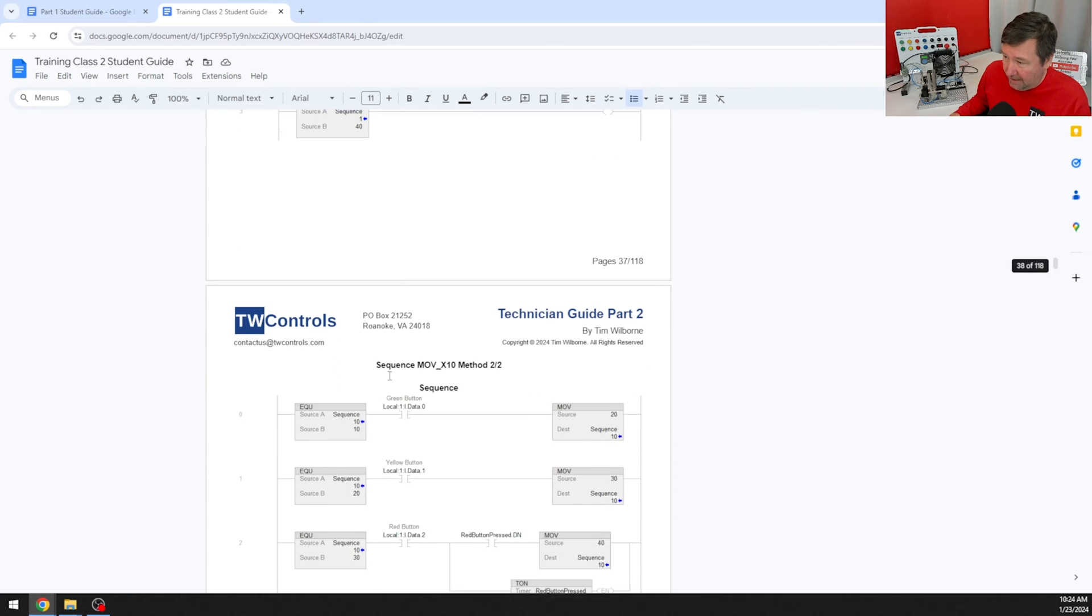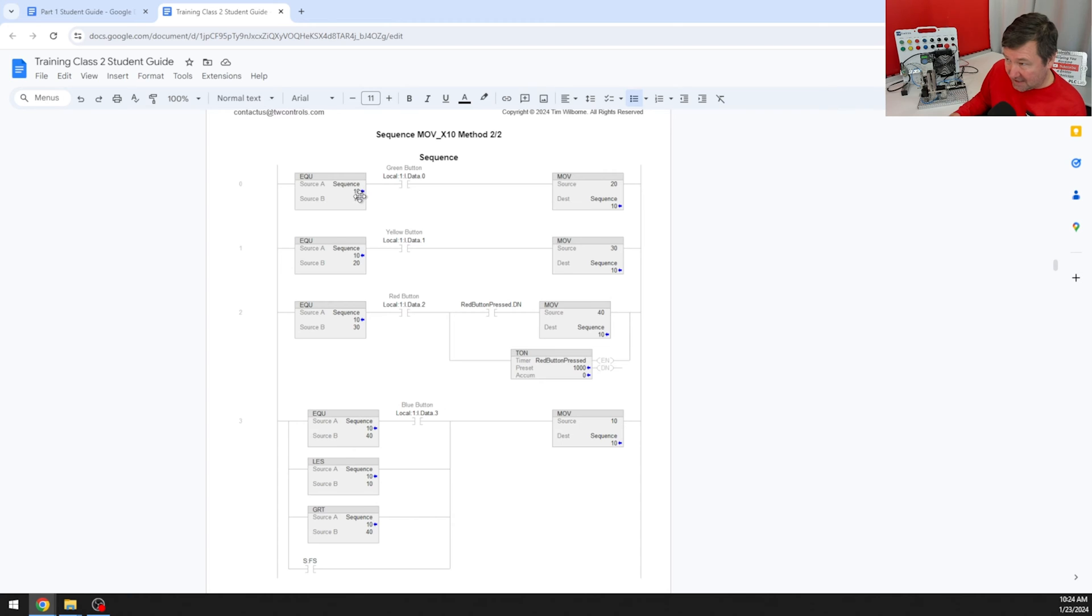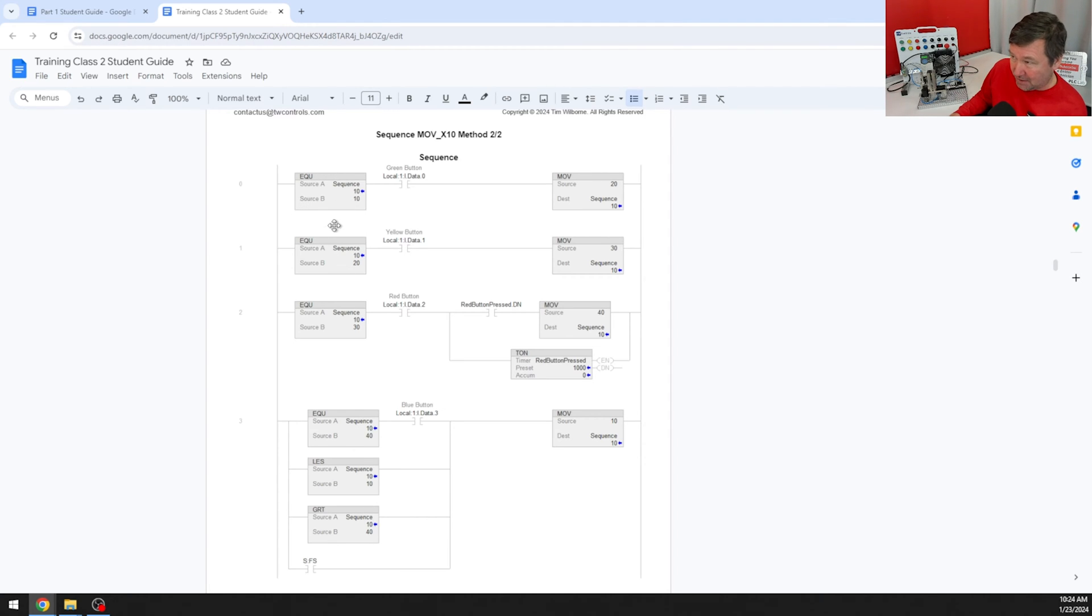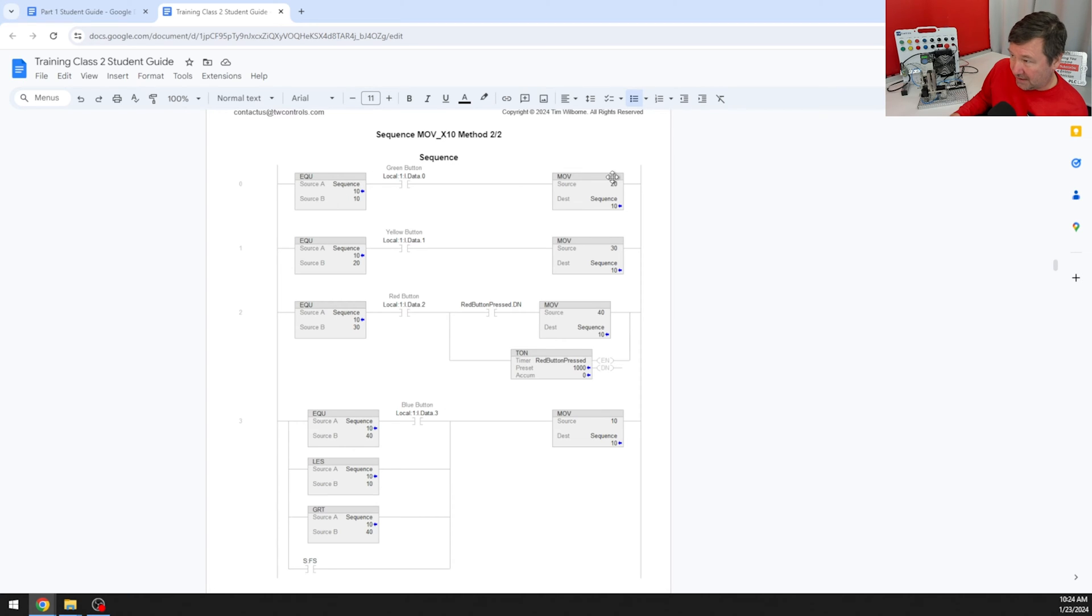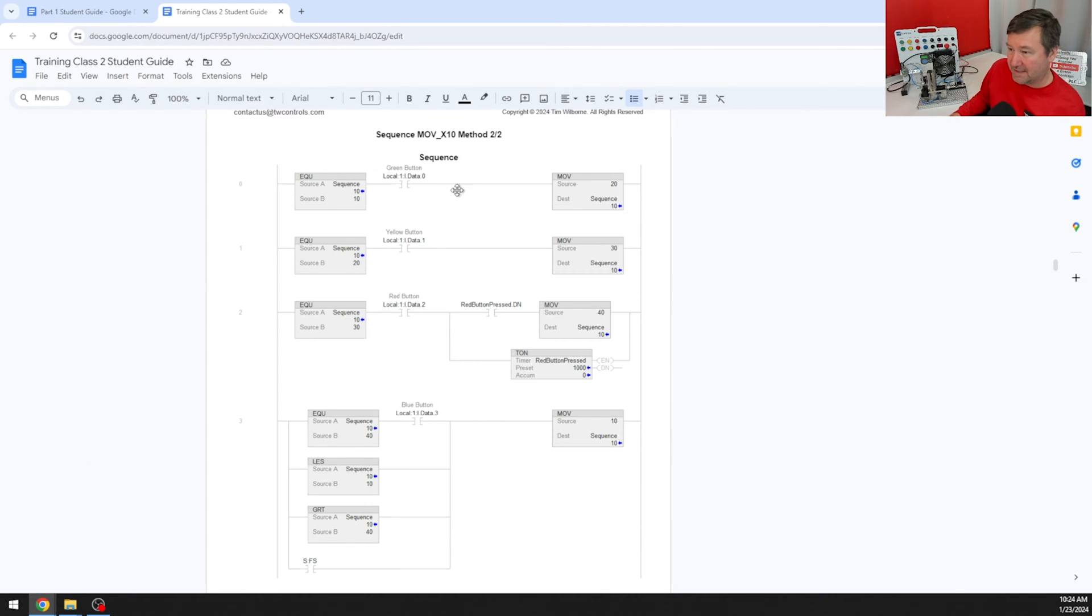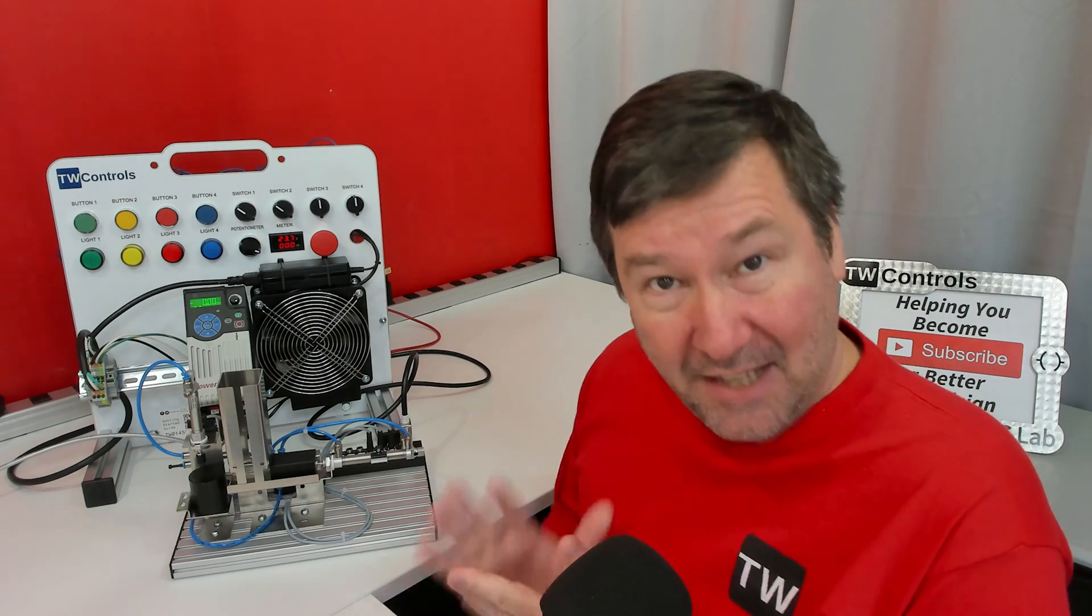We're going to have certain sequence steps. In this case, my first step is actually 10. That allows me to put one through nine above it later on. And since I have 10 and then 20, I can add in between here. So we'll have a step, and then when it equals that and whatever input conditions are made, we'll go to the next step and go to the next step. First, let's talk through what our steps are.